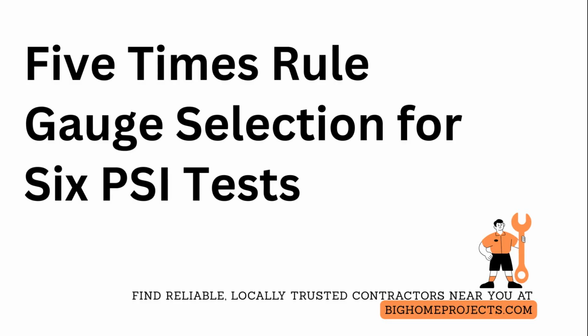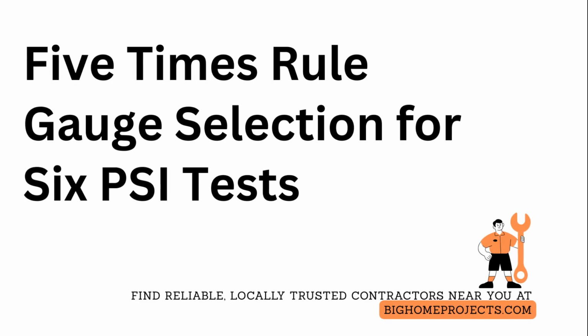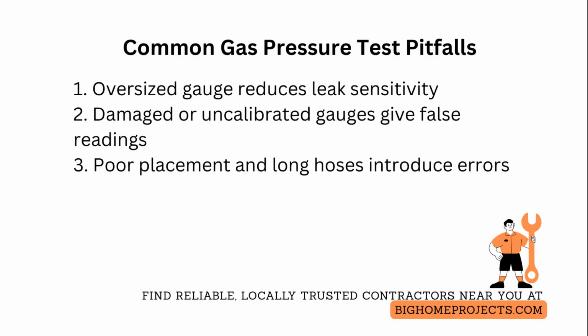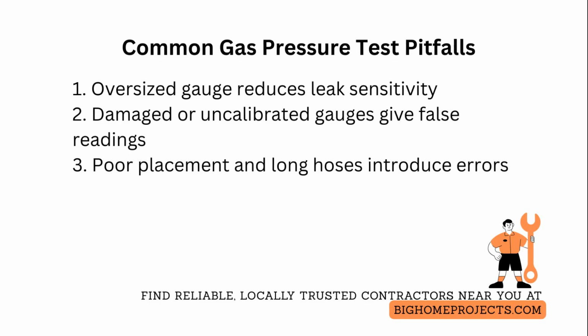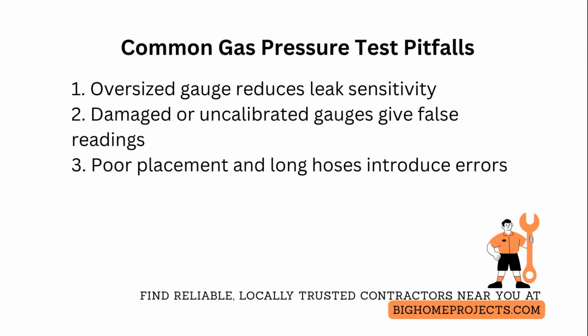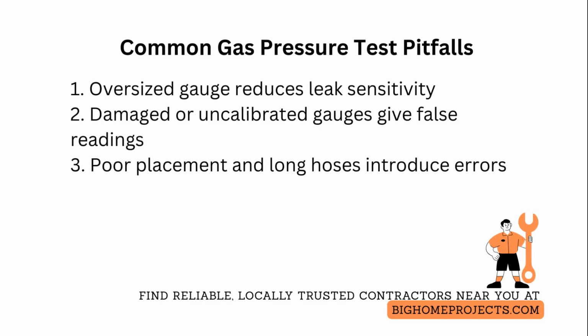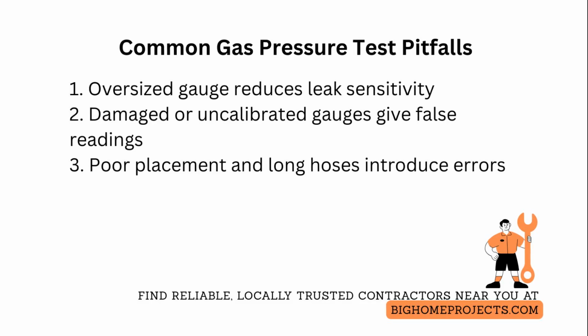Always use gauges with a current calibration sticker and a clear traceable certificate when required by code or insurance. And replace or recalibrate any gauge that shows wear, corrosion, or inconsistent zeroing. One of the biggest mistakes is using an oversized gauge designed for high pressures, which eliminates sensitivity to small leaks. Fix this by selecting a gauge with a full-scale range of about 5 times the required test pressure, or using a 30 pound per square inch gauge for 6 pound per square inch tests.